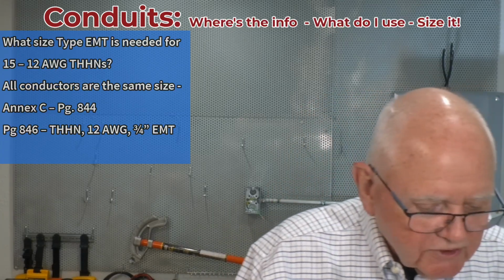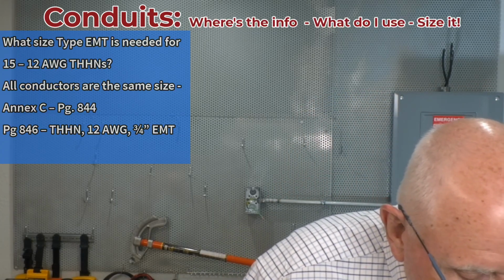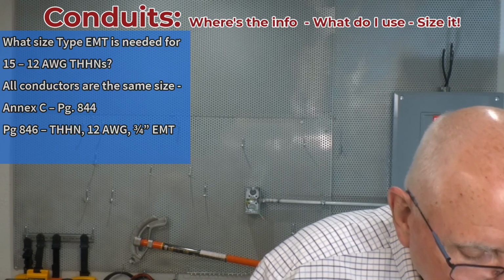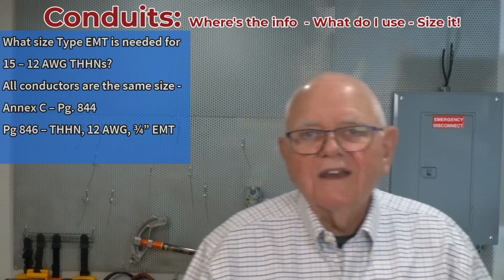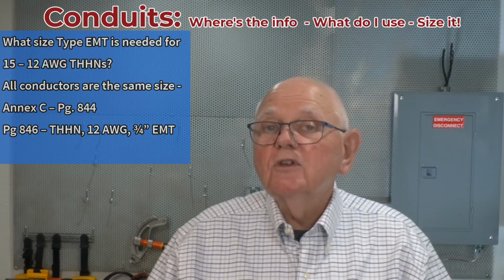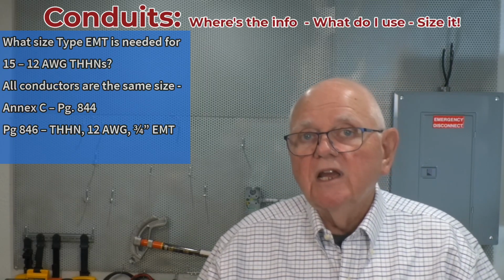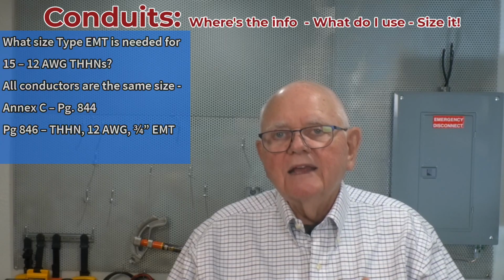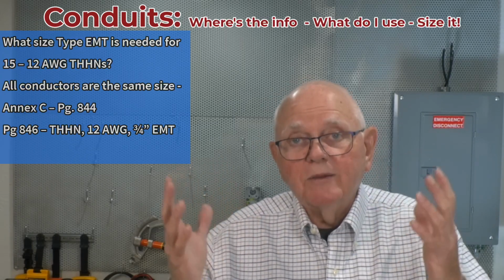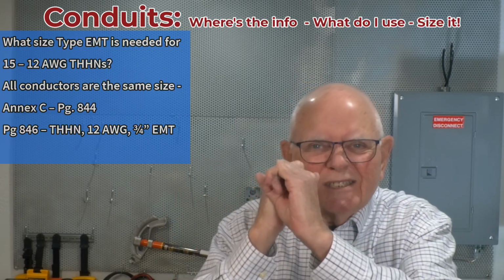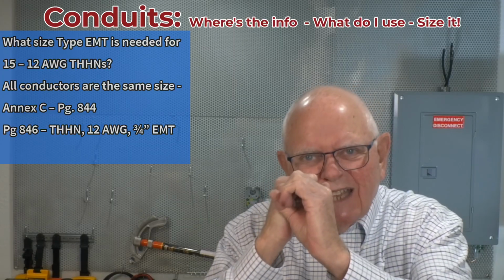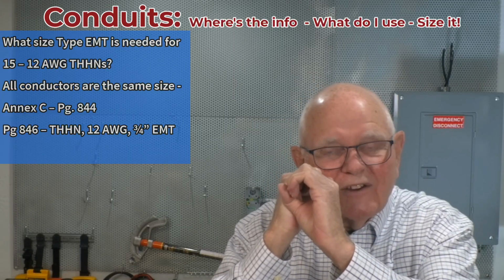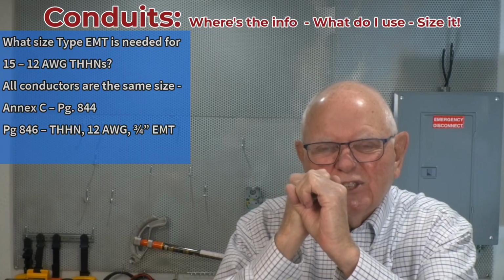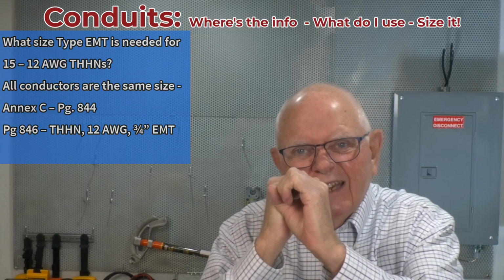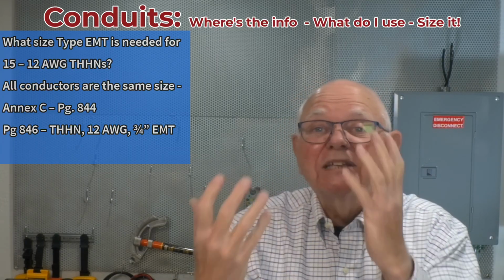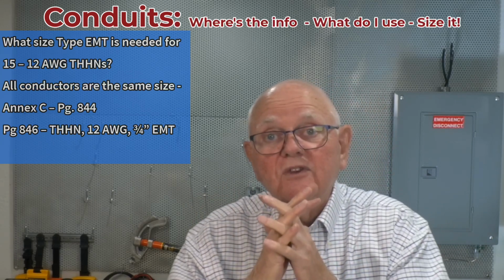So for instance, Table C1 is for electrical metallic tubing. C1A is for electrical metallic tubing with compact stranded conductors. If you look at the 2 tables, you'll see the differences. So compact stranding conductors, that's where when we extrude those conductors, when they're manufactured, they're just all compressed together so tightly that those individual strands are squeezed together. They're no longer round. There are some odd different shapes, but they're squeezed together so tightly that the interstices, the air voids in between the individual strands, are removed.